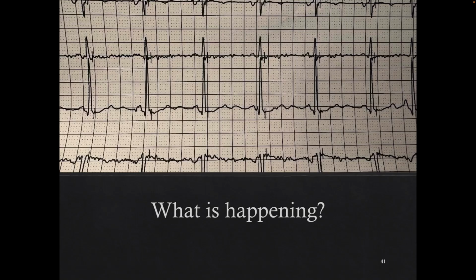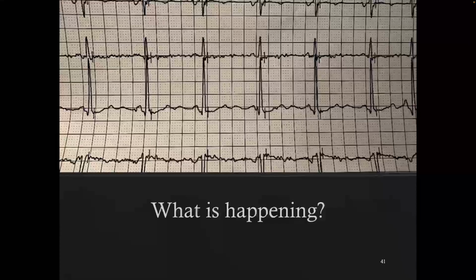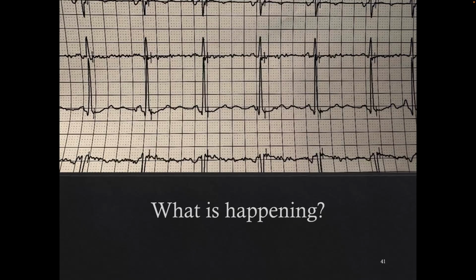It undersensed, right? So in the morning, everything was fantastic. Well, the ventricular signal was a measurement of, I think it was about 4.6. This is what we measure through here. When I went back, and the setting on the device, so 4.6, I think it was 2.8 millivolts, meaning that window was not really double of that, so there was a chance it was going to undersense just based on that setting, because the fence was a little bit too high. So I was like, oh, maybe I just need to change that. But then I went back and I remeasured the signal of the amplitude from the RV lead, and it was much smaller. It went from 4.6 to 1.9.